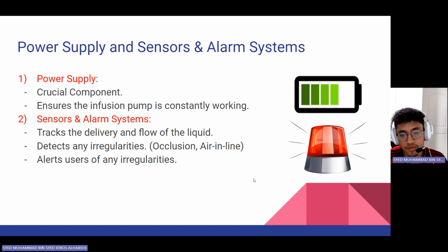As for the sensors and alarm systems, it tracks the delivery and flow of the liquid in order to ensure it is flowing at the set rate and is not overdosing the patient. It also detects any irregularities such as occlusion and air inline. Once these irregularities are detected, the alarm system will sound and alert the users to take the necessary actions immediately.